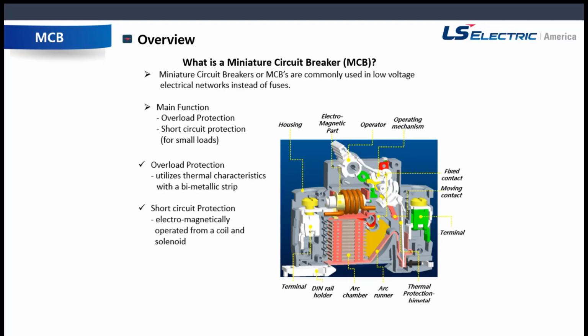So what exactly is a miniature circuit breaker? A miniature circuit breaker is commonly used in low voltage electrical networks in place of fuses. As we've said, they provide overload protection. And this is just a diagram of how they work on the inside. I know they look big and daunting, but how it works actually makes quite a bit of sense. We have the contact, and just the general operating mechanism. There's also an arc chamber and thermal protection bimetal to move the dial. All of that is used for overload protection. Short circuit protection is done through electromagnetic operation from a coil or a solenoid. So there's quite a lot going on within the miniature circuit breaker despite its size.